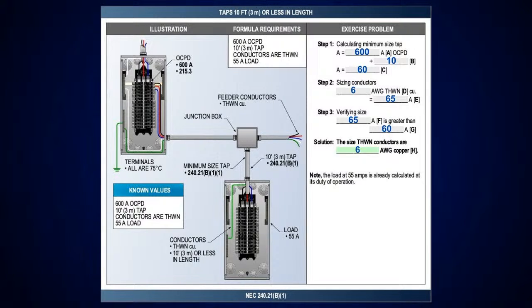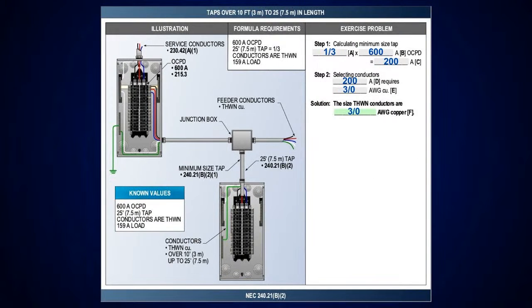I go over, look at table 310.16. We're using the 75 degree C terminals. Come down to the next size above at 65 amps, which is going to require a number 6 conductor. So therefore, we verified that the 65 amps is greater than the 60 amps. Therefore, the size THWN copper conductors are number 6. Very simple. Then I go to a 25 foot tap.